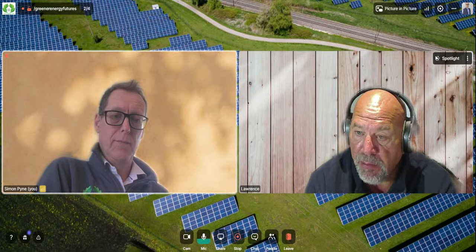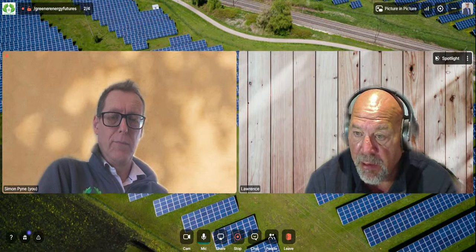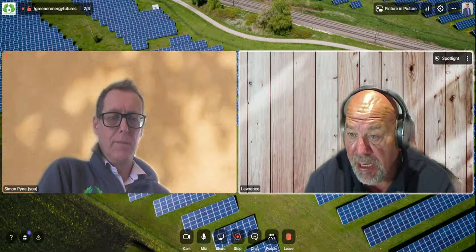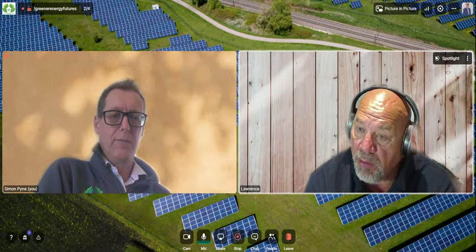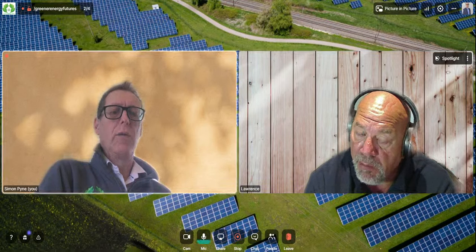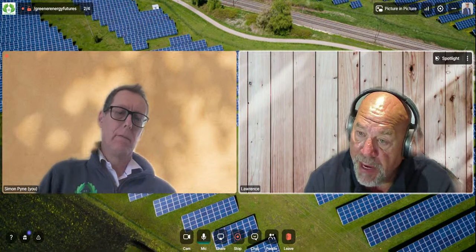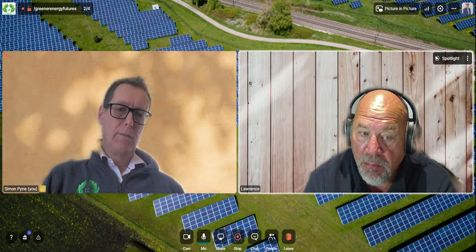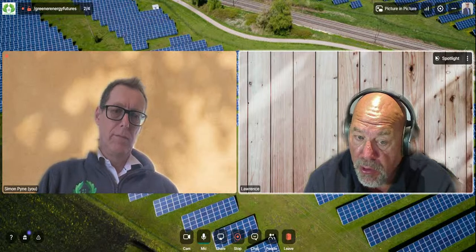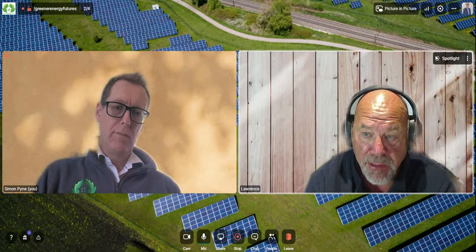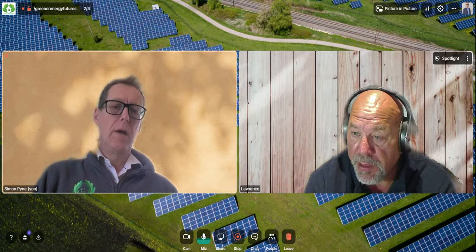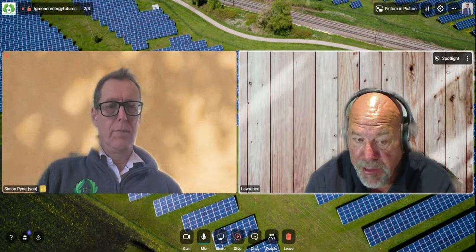I get people to clamp, if it's technically feasible, to get somebody to clamp it with a meter to look at the current the motor's pulling - I'm with you, yeah - and then you could work that into kilowatts. Then look at any opportunities to remove belt-driven fans and replace them with direct drive. Yeah, that's a really good win, and it saves maintenance.